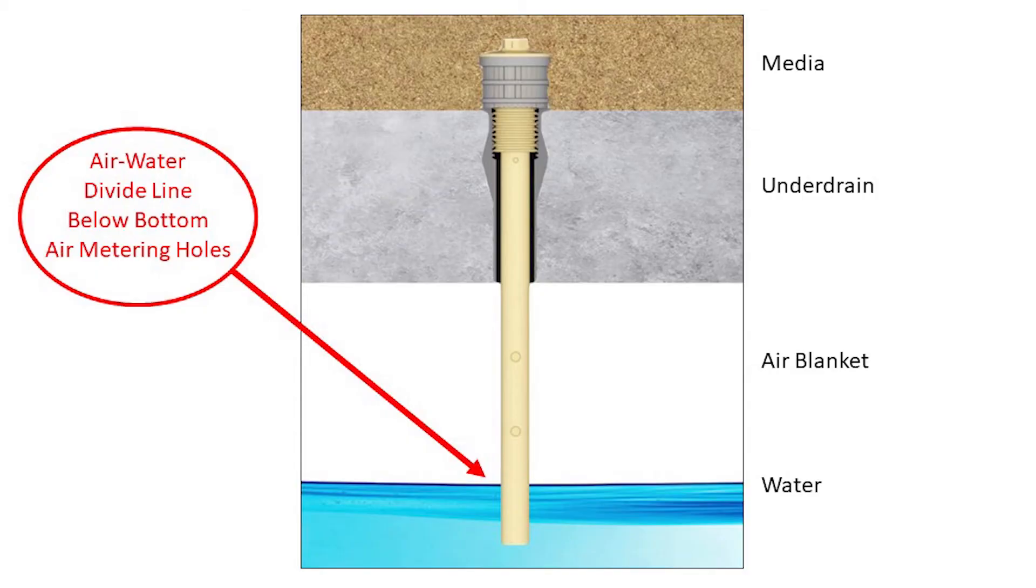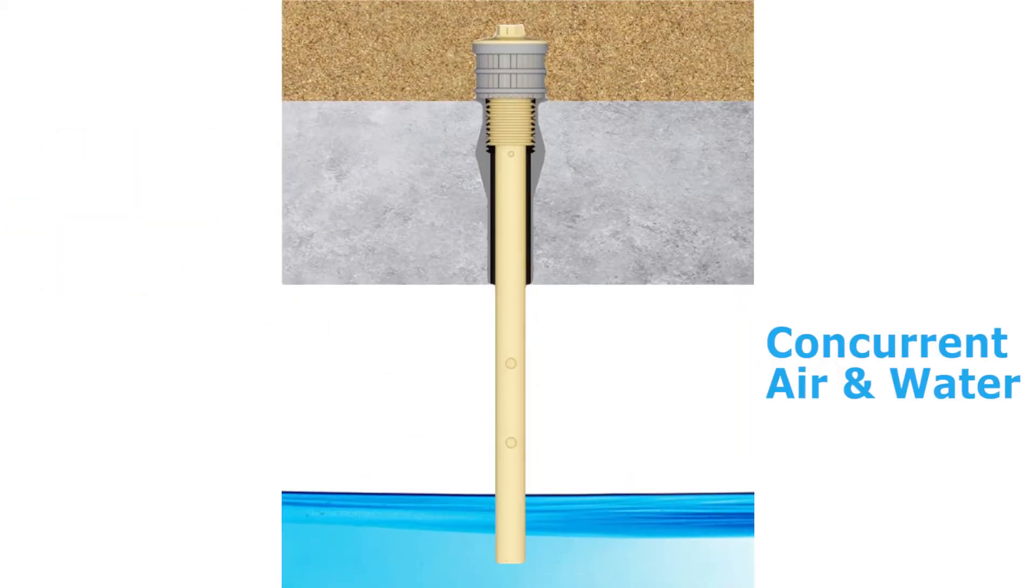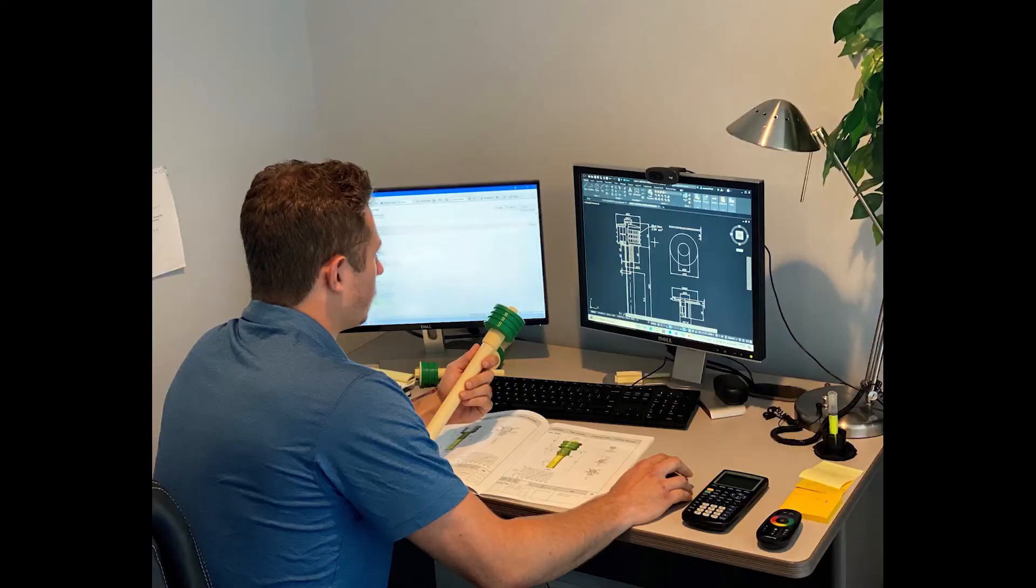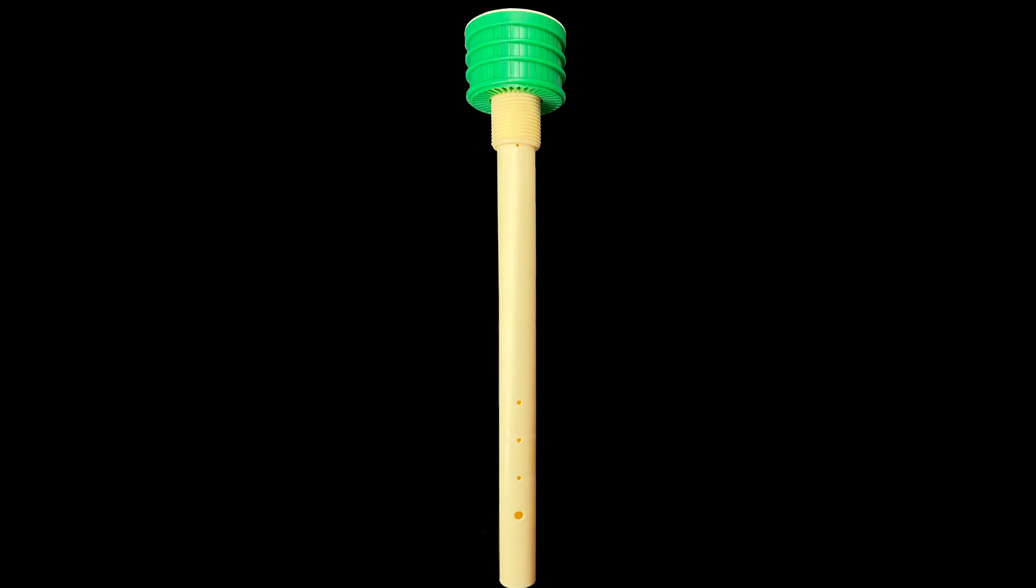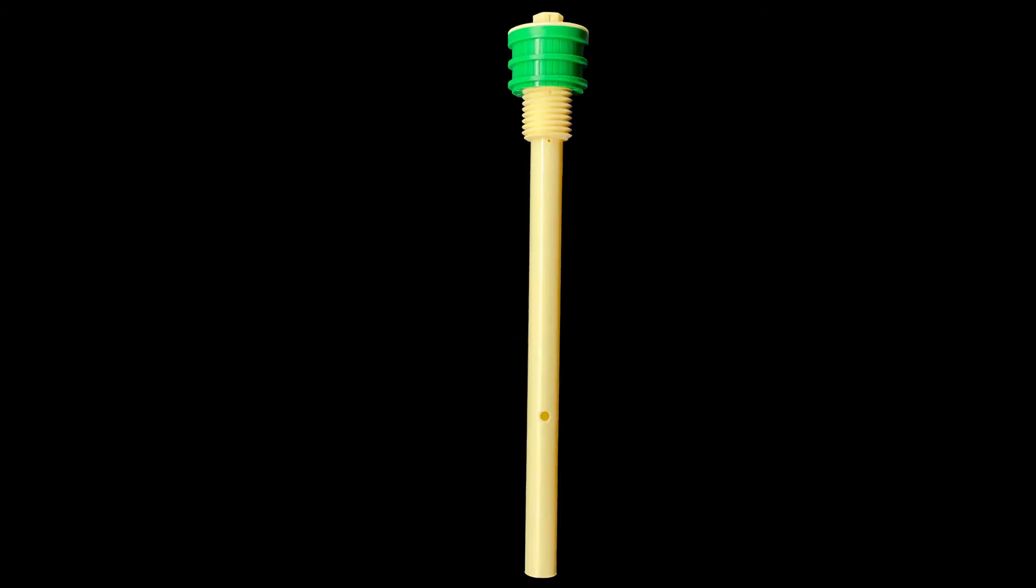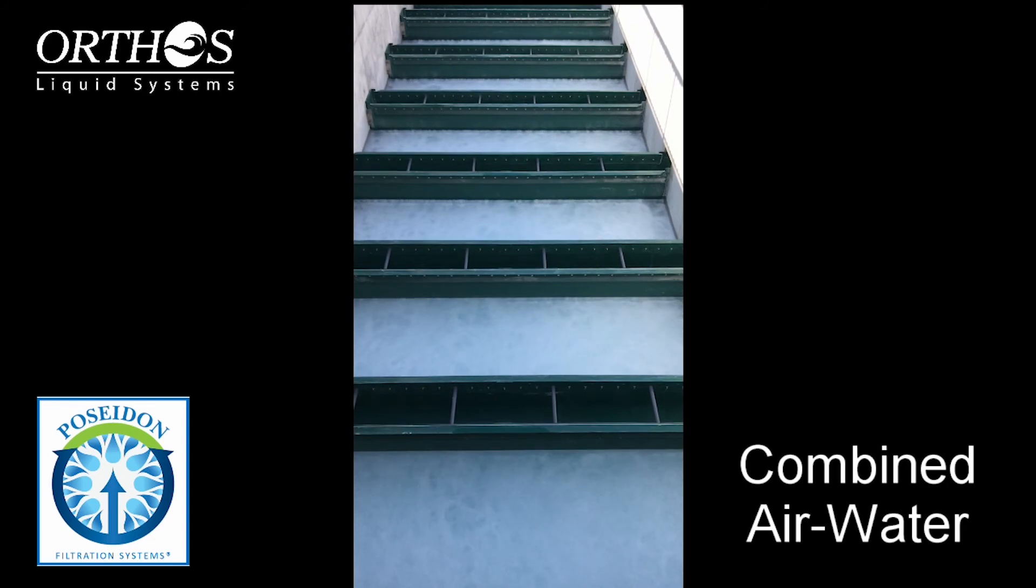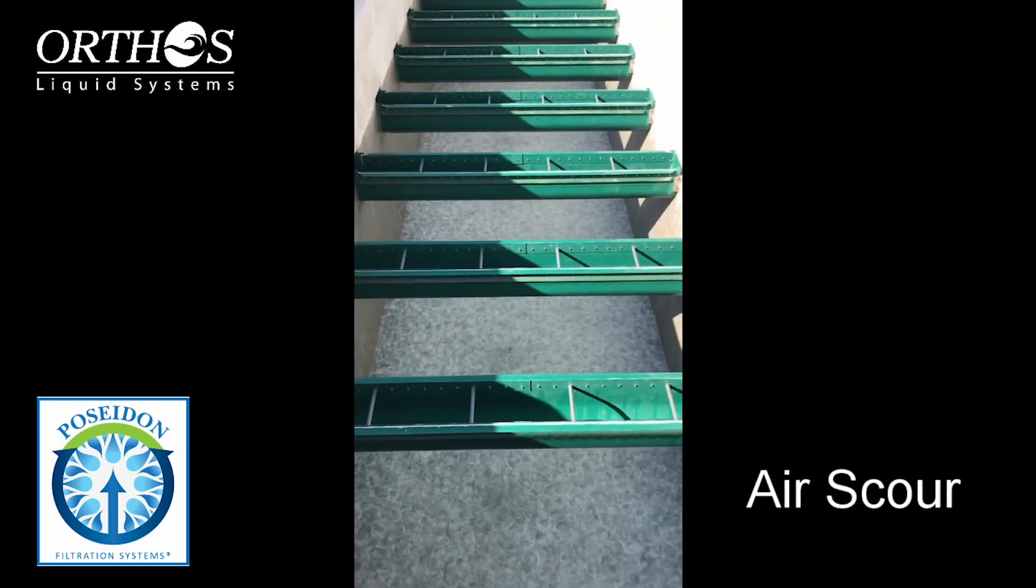For concurrent air water backwash applications, the air blanket is compressed within the plenum when backwash pumps are turned on, which adds some design complexity. Orthos engineering staff will select the proper combination of air metering hole quantity, location, and size to ensure excellent distribution during concurrent backwash as well as the air only initial phase.